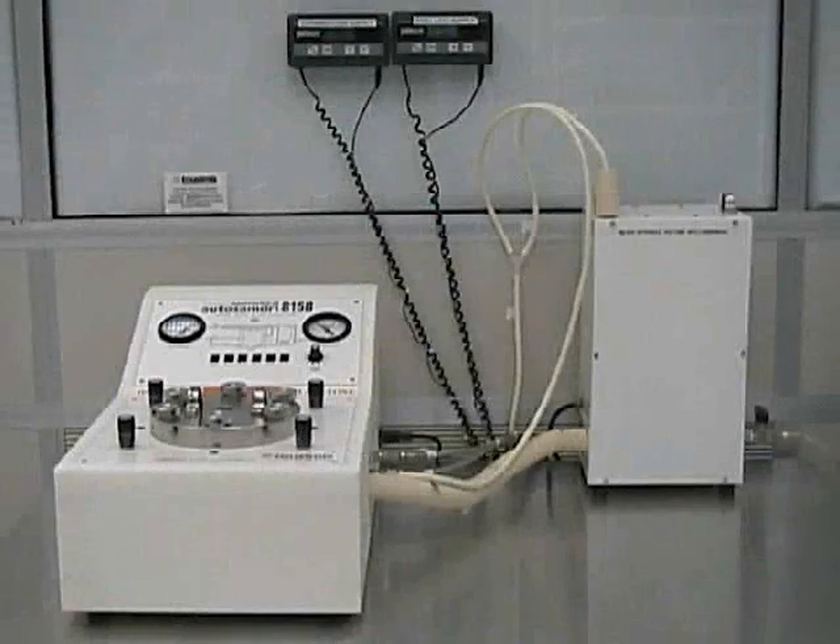The Tousimis Autosamdri-815B Supercritical Dryer is used for anti-stiction processing. Stiction is a common predicament in the fabrication of MEMS devices from surface micromachining. It occurs when surface adhesion forces are higher than the mechanical restoring force of the microstructure.